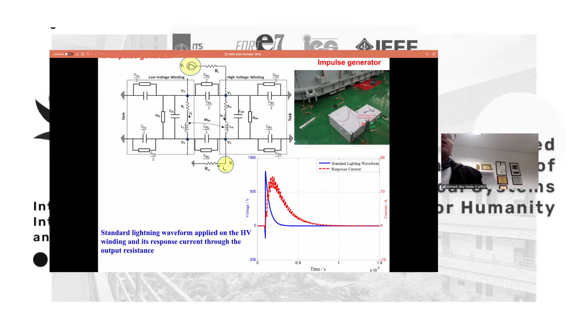We have done some of this work ourselves, using this pulse generator. We connected it to the transformer and found that yes, it can plot the FRA. What you see here is what we did using the impulse generator compared to the signature from the small device offline test, and they are identical. So this technique can be very practical and can be used for an operating transformer.